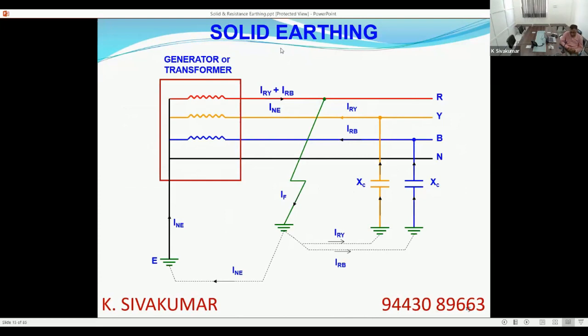But since interphase capacitance does not involve earth, that is not the point of discussion in this webinar. We are interested in the capacitive coupling between phase and earth only. Since R phase has got earthed, R phase capacitance gets short circuited, because the top plate of the capacitor will also be at R phase potential, and the bottom plate will also be at R phase potential, so it is bypassed. So there are two capacitances, Y phase capacitance and blue phase capacitance, which will also discharge into the fault.